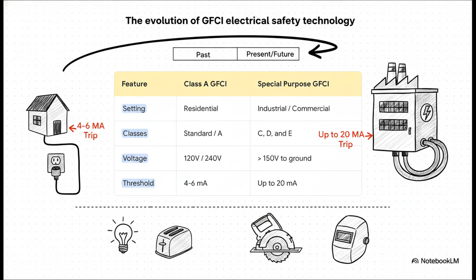While your home GFCI is super sensitive, tripping at just 4 to 6 milliamps, an SP GFCI is designed to allow up to 20 milliamps of leakage.